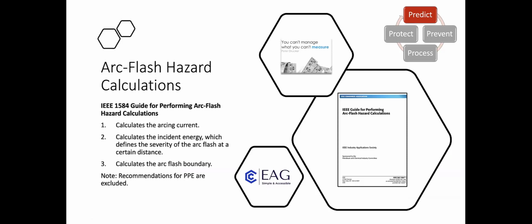The IEEE 1584 guide shown here on the right-hand side is a guide for performing arc flash calculations, and it's the most comprehensive means to evaluate the arc flash hazard, and it's an internationally recognised and auditable standard. But there are other methods described in the guide and later in the presentation, and I'll talk about those and how you can get those in the methods as well.